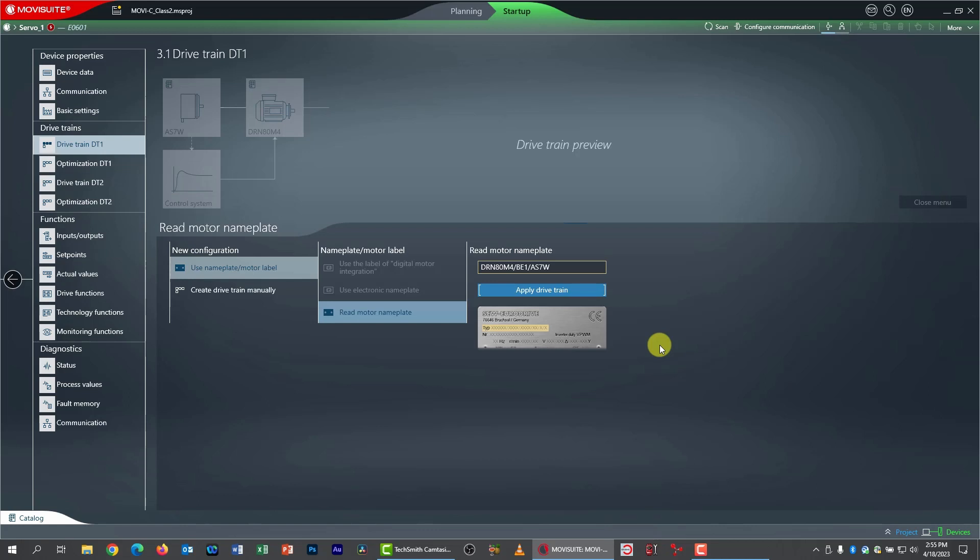it doesn't know there's an encoder there. It doesn't know there's an electronic nameplate. It has no idea what's in here. What I need to do is just key in enough of the drive nomenclature to commission the drive. I'm going to key in just the motor name, and I'm going to key in the brake. And that is it.